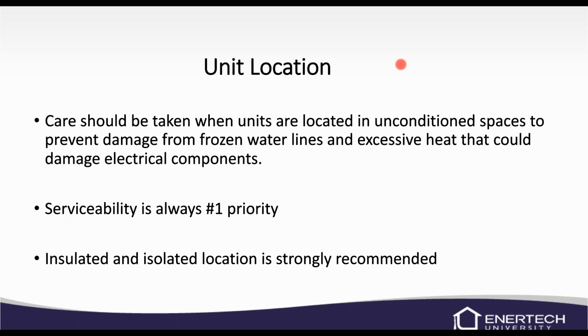An insulated and isolated location is strongly recommended. The unit is not loud. It is loud. We've got the door off of it. Sounds like a regional jet getting ready to take off. But with the door on, it's real quiet. So they really shouldn't hear it. And you don't have any refrigerant lines that could cause any vibration. You could have some water lines that might cause vibration, but I wouldn't set it right next to a bedroom wall.